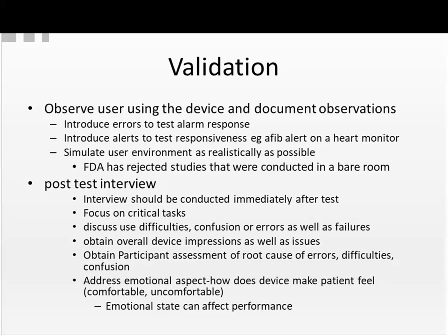Following the test, there's a post-test interview of each participant. The interview should be conducted immediately after the test. You want fresh thoughts, fresh observations. The interview should focus on critical tasks. You should discuss difficulties, confusion, errors as well as failures. You should obtain an overall device impression as well as discuss the issues.